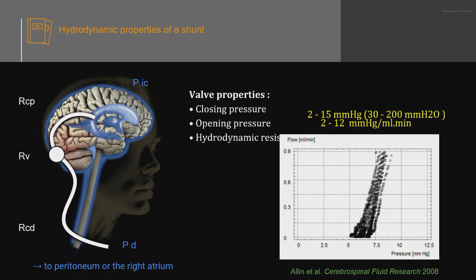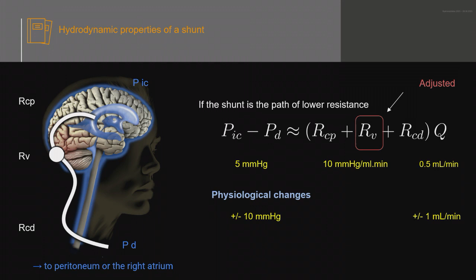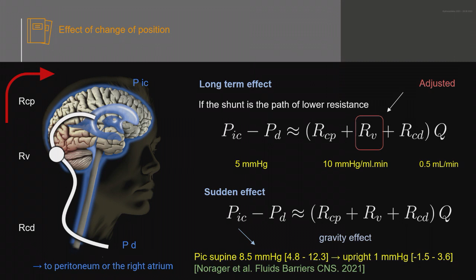So if the shunt is the path of lower resistance, then it will be the main resistance in the system. And then you just add up, because it's in series, the catheter resistance and the valve resistance. This you can choose. So if we have typical value for the resistance here, and typical production of CSF, we find the same drop of pressure I showed before. And if you have physiological change of about 10 millimeters of mercury, we have this change of outflow. But now, if you change the position, then there will be a lot of things going on. You will have a sudden effect when you change position, where the intracranial pressure will drop, and this has been reported in several publications. So this, we would think that it might reduce the outflow.